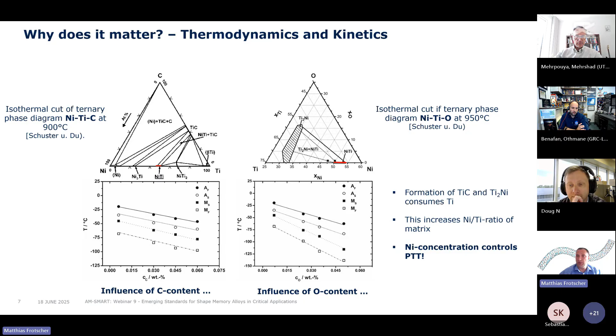Another reason for the importance of carbon and oxygen content in nitinol is the fatigue performance, as both secondary phases are hard and brittle and can lead to crack initiation and subsequent fracture under fatigue conditions, like those frequently encountered by medical devices, which typically stay in the human body for a long time. In general, it has been found that the oxygen-rich intermetallic phases are worse than carbides.